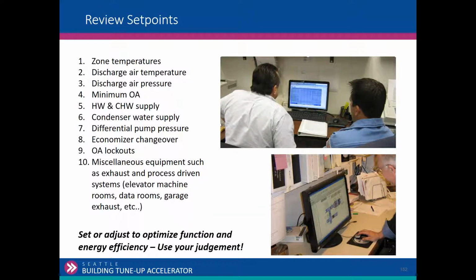Set points, we're going to rely on your judgment. Do these set points make sense? Zone temperatures, I'm kind of like whatever it takes to maintain comfort. Changing zone temperatures is pretty personal, and I don't want you creating comfort issues. If they need it to be 75, give it 78. What happens at night? Is there a setback on that? This building is pretty aggressive. It defaults to 68 degrees, but allows the occupants to set it up. So it's kind of like the adaptive comfort model.